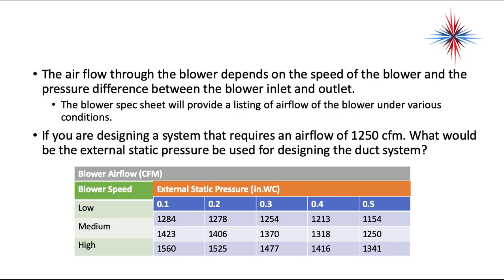The airflow through the blower depends on the speed of the blower and the pressure difference between the blower inlet and outlet. The blower spec sheet provides a listing of airflow under various conditions. For example, if you're designing a system requiring 1,250 CFM, you'd use a blower speed of medium and an external static pressure of 0.5 inches water column. The total external static pressure equals the static pressure of the supply plenum plus the static pressure of the return plenum — drop the signs, add them together as an absolute value.